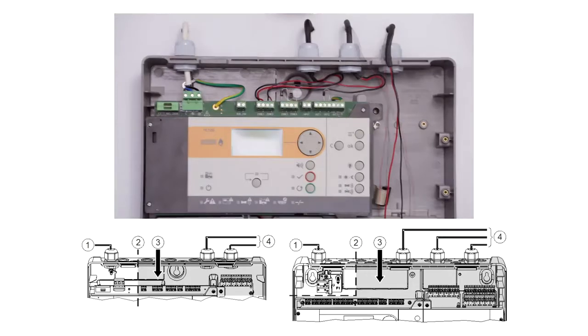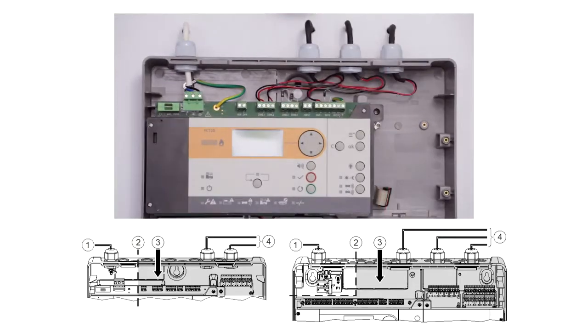These field devices are the detector lines and the control lines, like contacts or sirens. To provide a safety zone between the high voltage and the low voltage area, you must use cable gland 4. All detector lines and monitored outputs must have the required end-of-line element on the end of the cable. This is necessary in order to monitor the line. If you don't use lines in your project, put the end-of-the-line element directly into the panel.